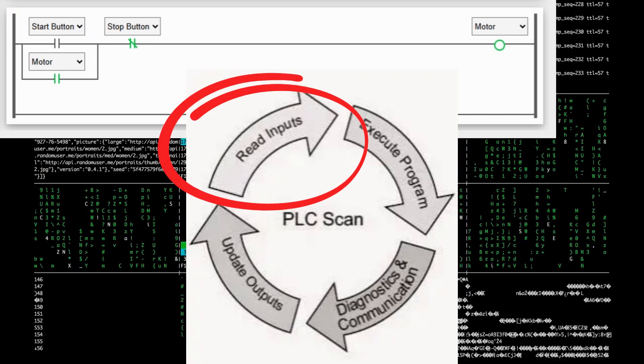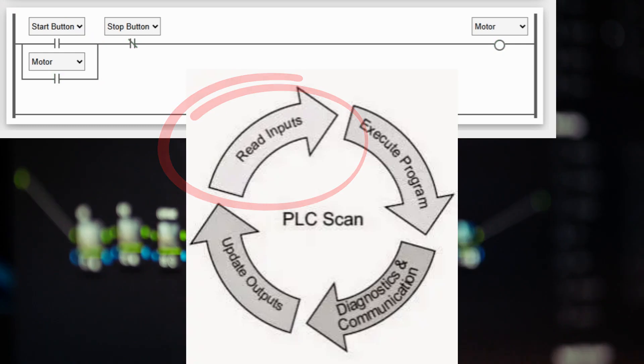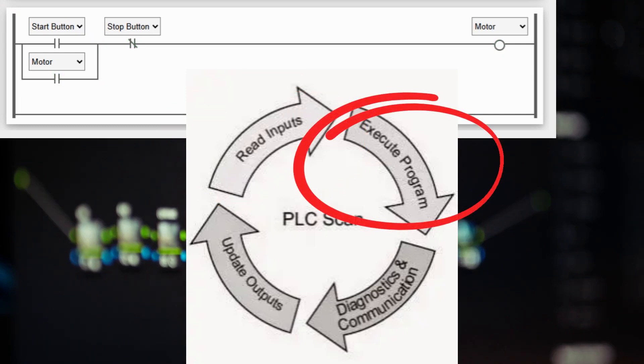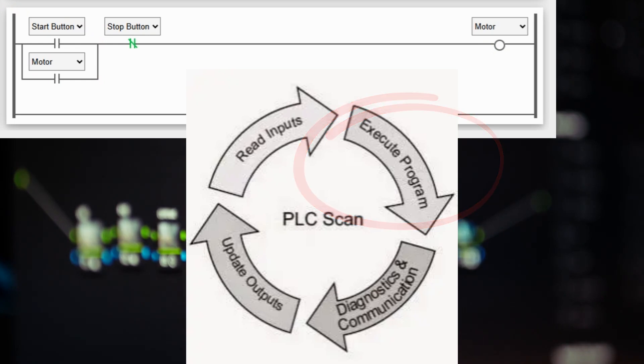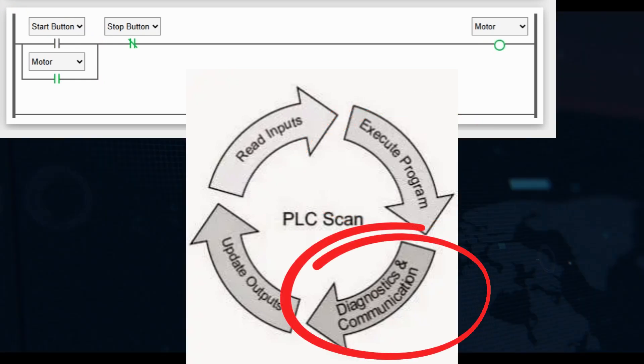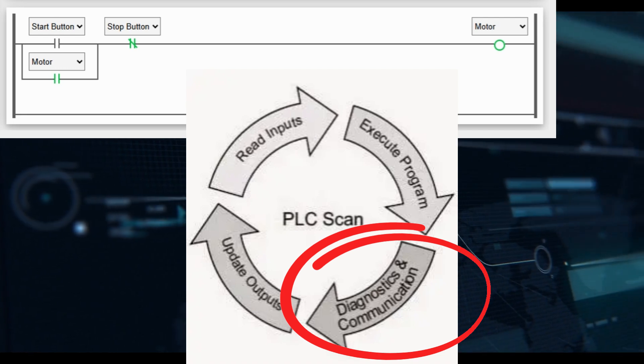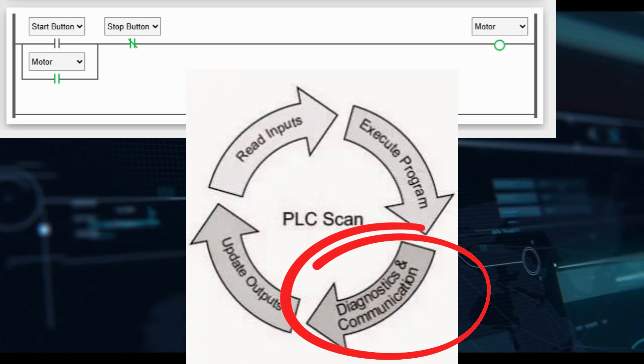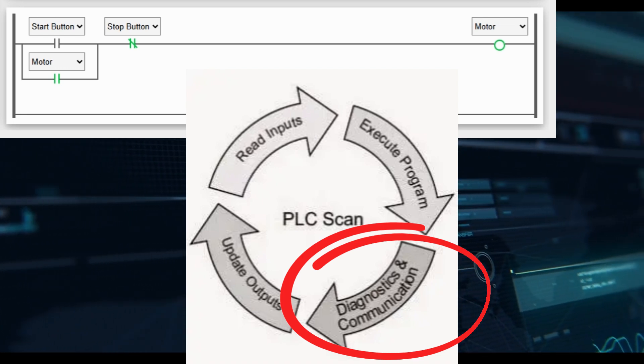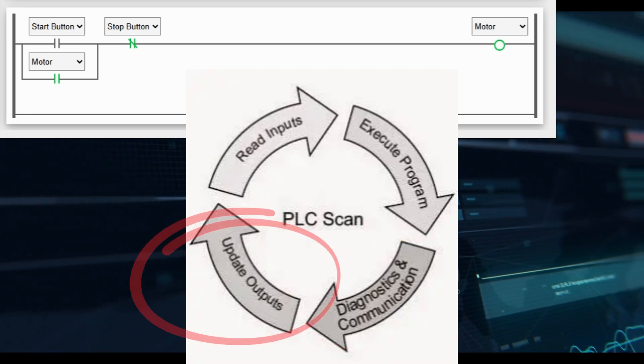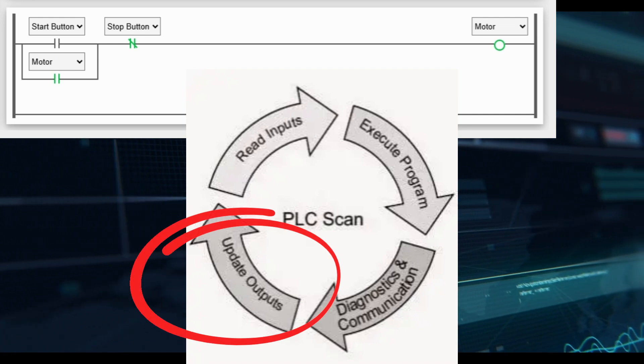Step 1: The inputs are read. Step 2: Your program is solved from left to right, top to bottom. The output from the previous rung is available for use by the next rung. Step 3: Communication and diagnostics are performed. This step may or may not happen depending on the PLC simulator used. Step 4: The outputs are written.